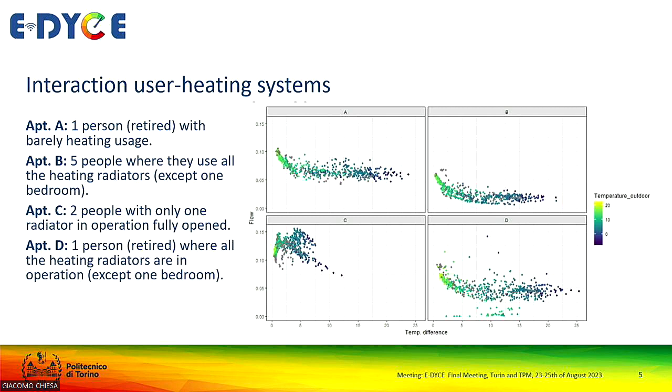And what we can see, these are the 3 apartments that look very much alike. These are the apartments that actually have very different behavior, have very different room temperatures, but the last one, this is the one that behaves differently. And this is mainly because this is the apartment, we can see from the measurements, that is heated by only 1 radiator, 1 water-based heater, and thereby the heat released into the space is not used efficiently.